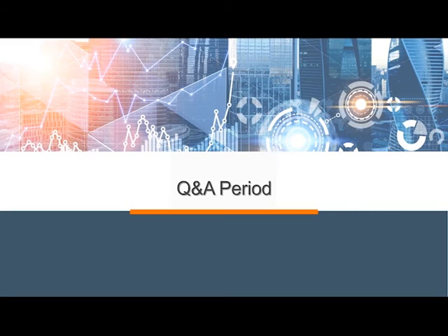We often come across buildings like this, and the first step is to see if our AI platform can look at what's being derived from the BAS and tag the points appropriately. And if it does, that's great. But that may not be the case all the time, in which case we actually rely on actual human beings to look at the data and apply the right tags. And it could be a combination where we use the platform to assign tags appropriately, and then our staff, we have building application engineers who take a look at the actual data set and then apply tags.